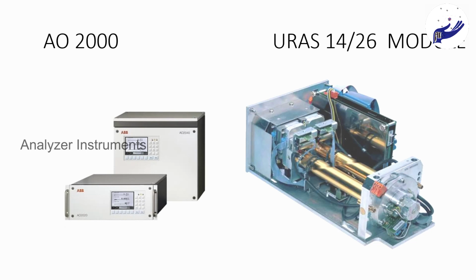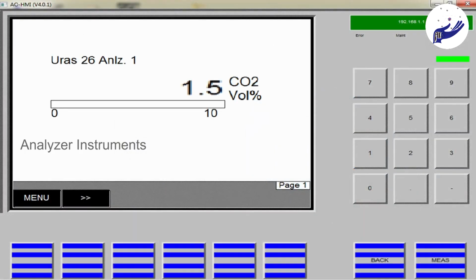Most important, before starting the calibration, make sure your zero cylinder is open and all the associated valves are open for the calibration. Ensure all the safety precautions are done properly. This is how your home screen looks. This is the URAS 26, and we are using CO2 for the calibration. CO2 is the measuring component. Now we will check how to do the zero calibration.